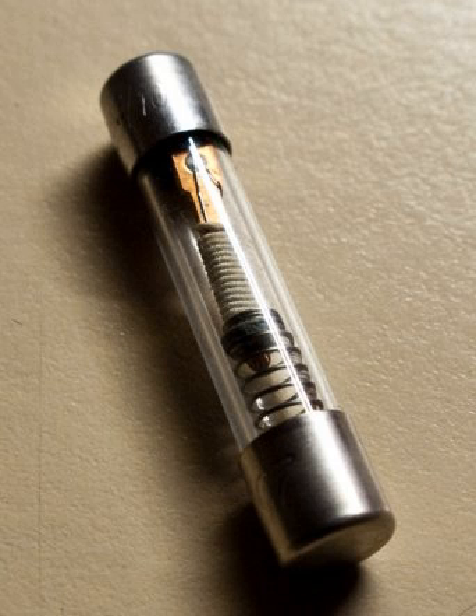Semi-enclosed fuses are fuse wire carriers in which the fusible wire itself can be replaced. The exact fusing current is not as well controlled as an enclosed fuse, and it is extremely important to use the correct diameter and material when replacing the fuse wire, and for these reasons these fuses are slowly falling from favor.